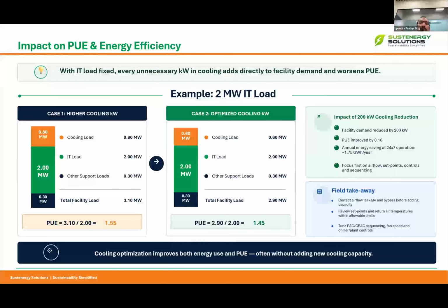So this slide is just to show the impact of reducing our cooling power on the overall PUE. We have shown by example that if a 2 megawatt IT load and our cooling load is around 0.8 megawatt, other loads 0.3 megawatt, then the existing PUE is 1.55. The practically possible reduction in the cooling load is 10 to 20%. So if you reduce the cooling load by 200 kilowatt, then our PUE will come down to 1.45. So this is just given as an example.